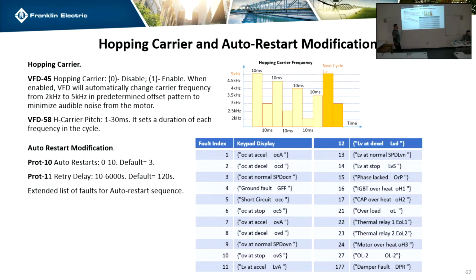So that's the amount of tries it will do in 120 seconds? No, it will do that many tries with that delay. So if it trips, it'll wait 120 seconds and try again. And is there a total time for all the restarts? No total time. Well, it's 120 times 3.